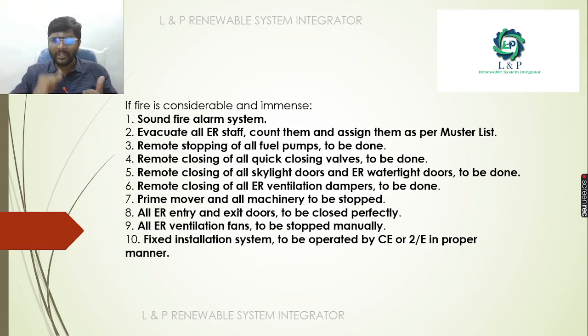Remote stopping of all the fuel pumps to be done, and remote closing of all quick closing valves to be done, and remote closing of all skylight doors and engine room watertight doors to be done, remote closing of all ER ventilation dampers to be done, prime movers and all the machineries to be stopped, all the engine room entry and exit doors to be closed perfectly, all the engine room ventilation fans to be stopped manually, and the fixed installation system to be operated in a proper manner.